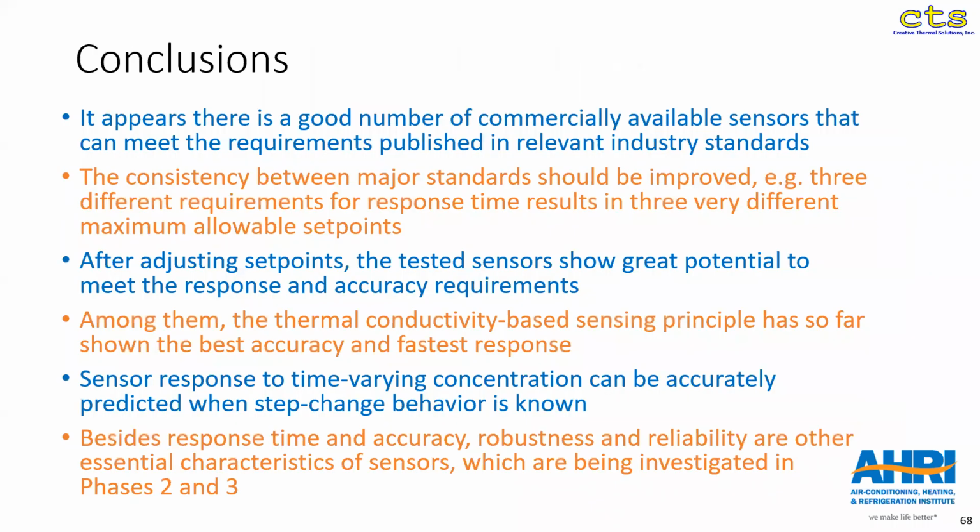And this brings us to the conclusions. So from the first phase, we have seen that there's already a good number of commercially available sensors that can meet the requirements in the relevant industry standards. So that is good news. We have also identified, of course, that there's some consistency issues between the major standards.